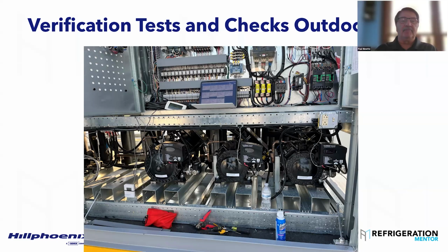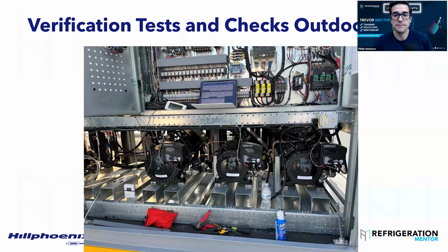Oh yeah, we've had a couple jobs like that where we go to start up, and because that's one of our checkpoints, we carry a magnet. Real simple test. Tap it with a magnet, and you can also tell by the color band that's on the pipe. Plus, it'll be listed at 130 bar. But yeah, we've had a couple contractors that we've had to have cut out and repipe the discharge. So yeah, it's happened.